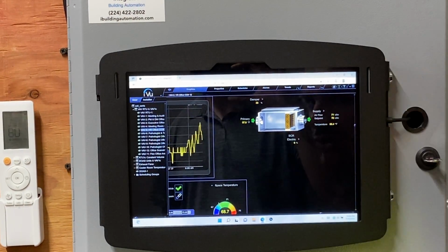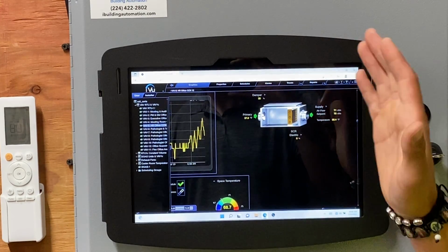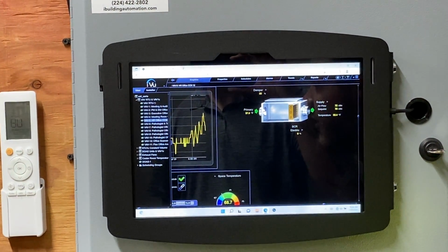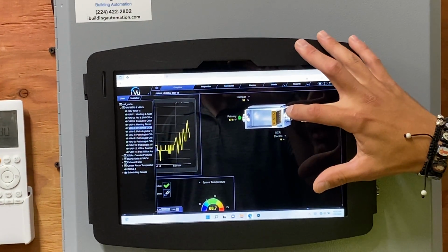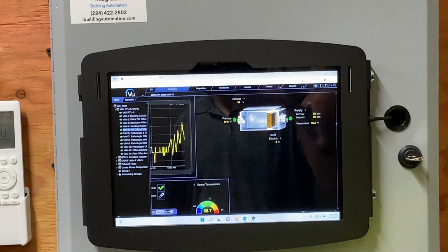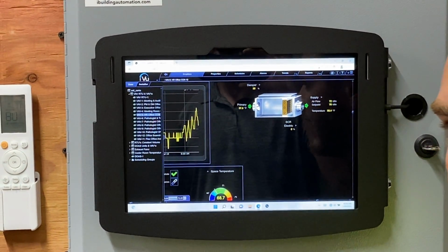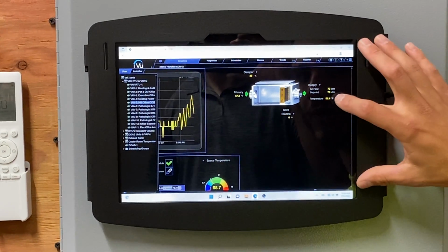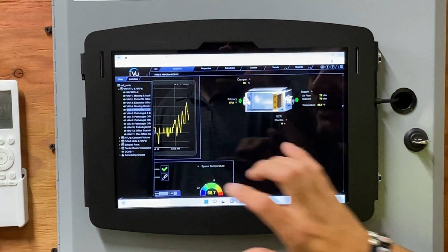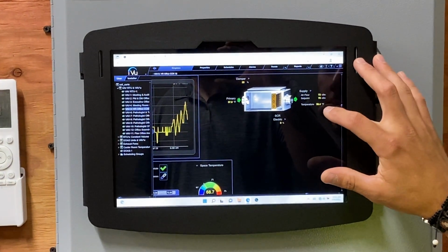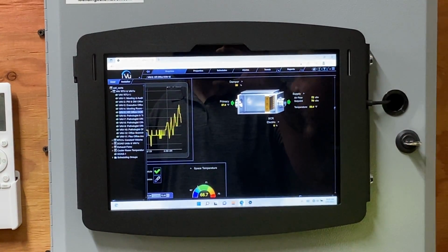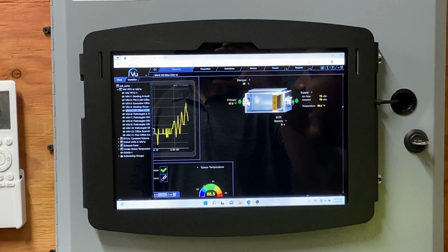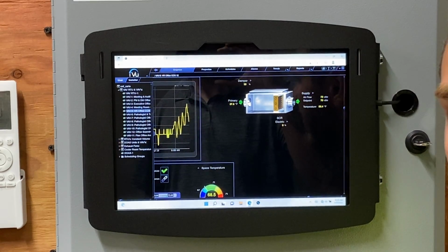The graphic actually does move as things change. When this damper does open 100%, you will see the graphic turn. And when the SCR heat lights up, you will see it glow red. But I always like to reference, like I said, your outlet temperature versus your inlet temperature. These boxes can produce up to 120 degree supply air temperature, depending on what type of primary air we have.